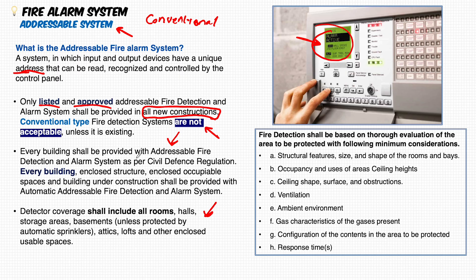Where must the fire alarm system be provided? In schools, hospitals, residential buildings, workshops, or warehouses? Every building in the UAE shall be provided with an addressable fire alarm system — every enclosed structure, enclosed spaces, and even buildings under construction. Temporary offices on construction sites shall also be provided with the automatic addressable fire alarm system.